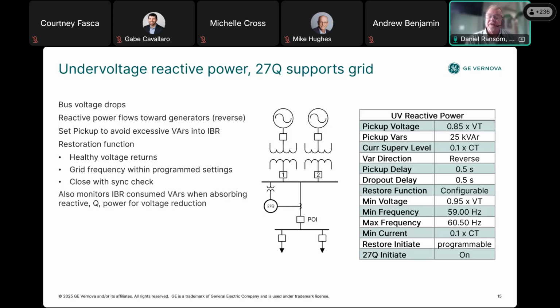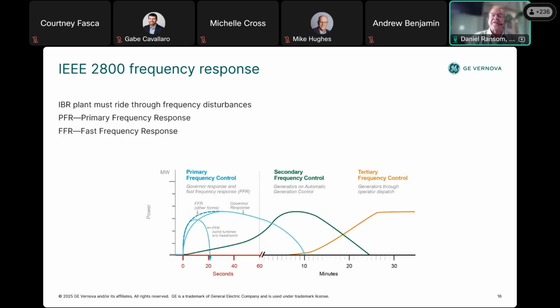Sometimes the IBR must accept VARs, take in VARs, to reduce an overvoltage condition on the system. So you can set the element to also monitor that condition. And now we come to frequency. We've been talking mostly about voltage ride-through. Frequency ride-through is also very important in how it affects the power provided by the IBR plant. The standards say that the plant shall ride through a disturbance and maintain synchronism with the connected grid according to frequency. So the frequency response is divided into two parts, the primary frequency response and the fast frequency response. The standard allows for adjustments to remain within volts per hertz limits, including the IBR units, transformers, and supplemental devices. For NERC PRC-024-3, the required responses are based on region, Eastern, Western, ERCOT, Quebec, etc., and your region.